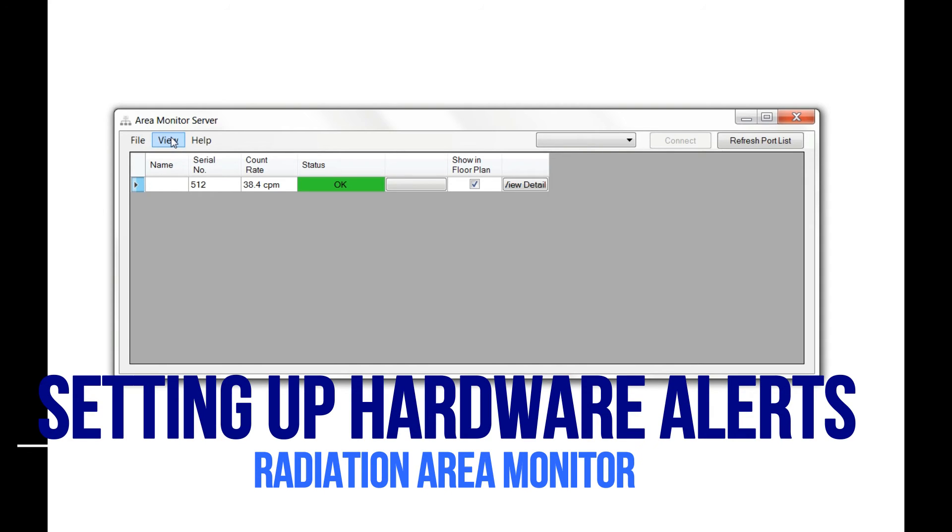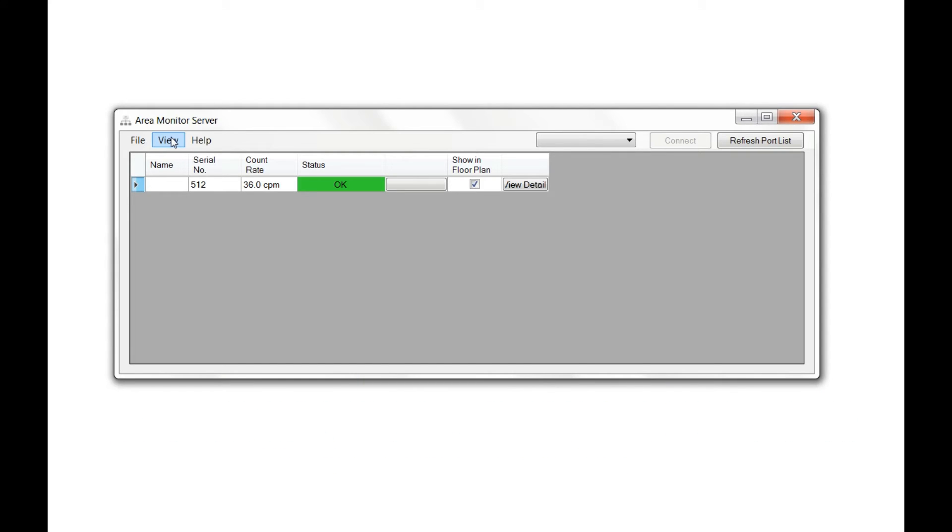That last part was about setting up software alarms. This next part is about setting up hardware alarms. The difference is the software does not need to be connected to the area monitor to send an alert over the network. All it needs is an Ethernet connection and access to the Internet.